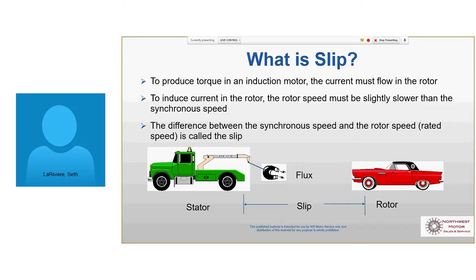So what's happening when the motor is running is we start a magnetic field rotating. You know, the very first slides we showed with the cross section of that 60 hertz cycle across the way. All that's really doing is setting up a rotating magnetic field that the rotor is trying to catch the entire time. It never does. It always lags slightly behind. That amount that it lags slightly behind is called slip, and it's that attraction that produces torque. If those two were locked together, there'd be no torque. They're just rolling around together. The fact that that is always behind and chasing, that's your torque producing element.